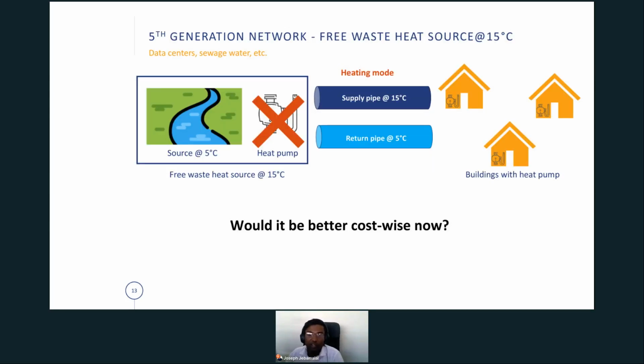But in the investment cost, initially we said we need a heat pump because we only had a temperature of 5 degrees Celsius, so we had both centralized and distributed heat pumps. In case you already have a free waste heat source available at 15 degrees Celsius, then we don't need the centralized heat pump. We can directly use the 15 degrees Celsius to supply, and then we only need distributed heat pumps.